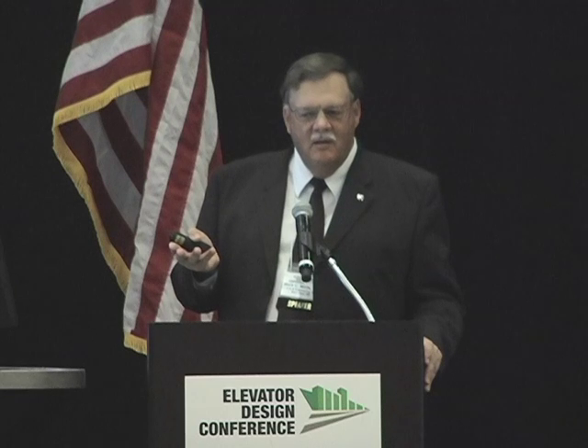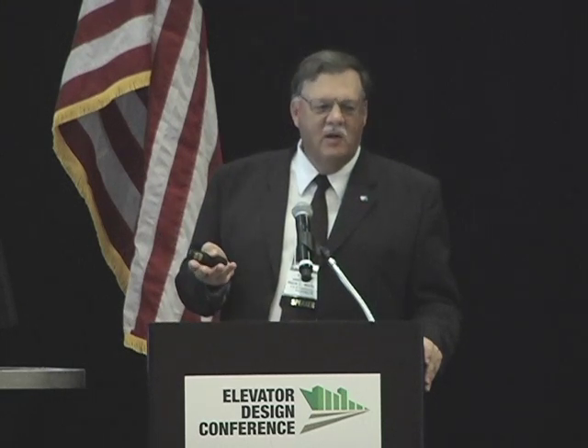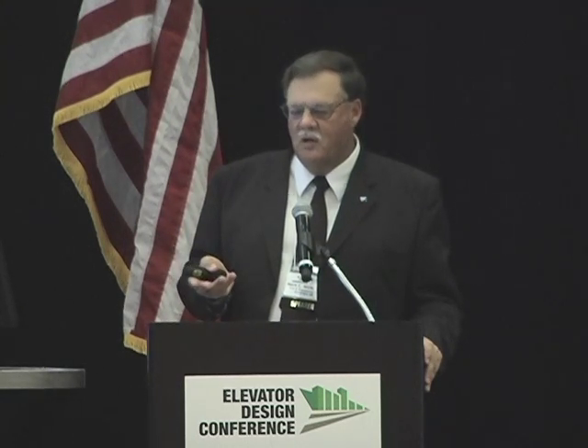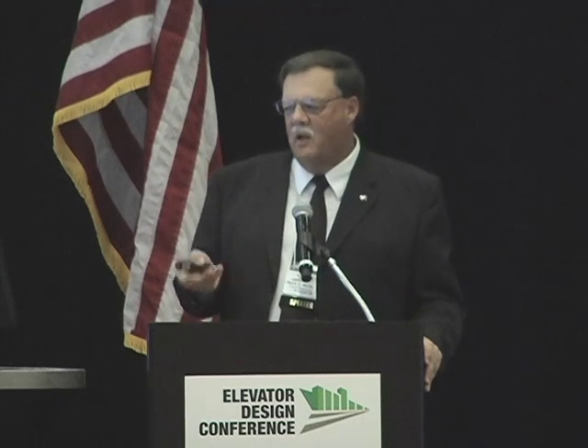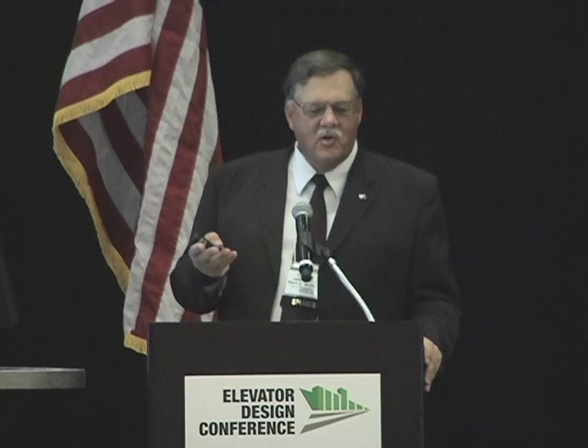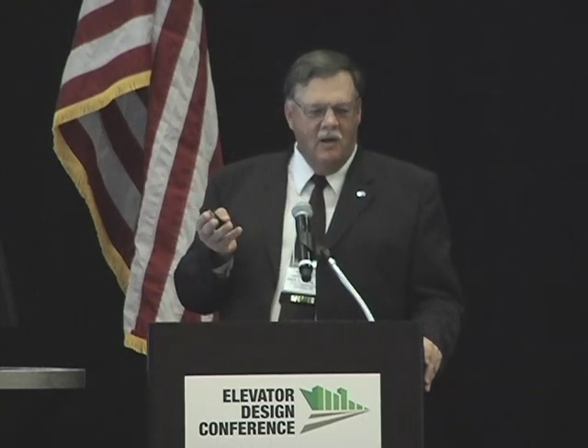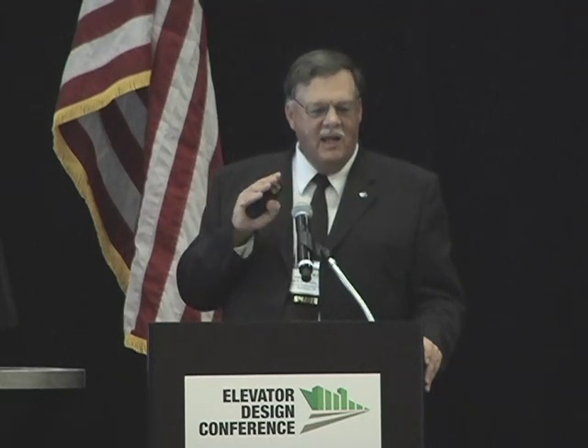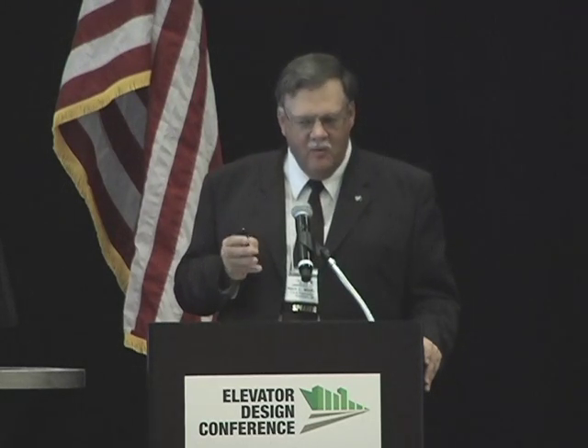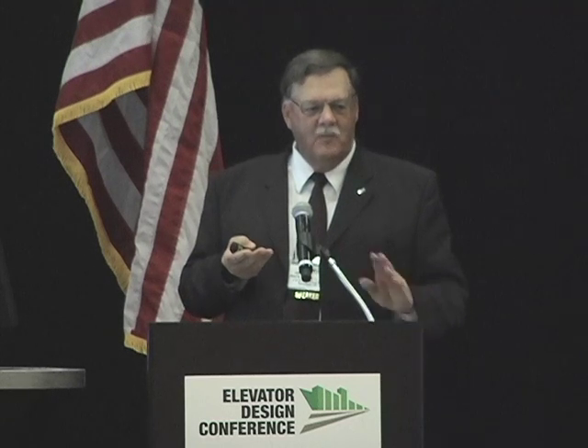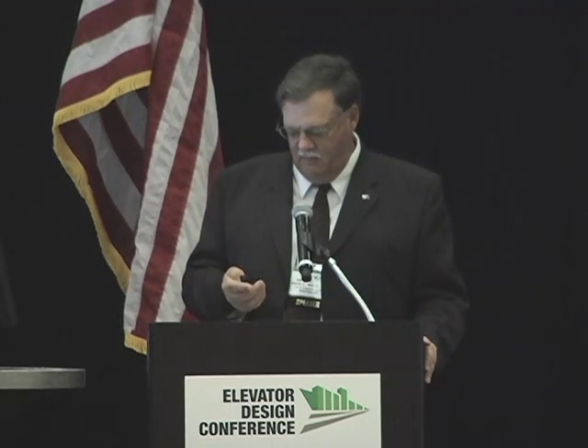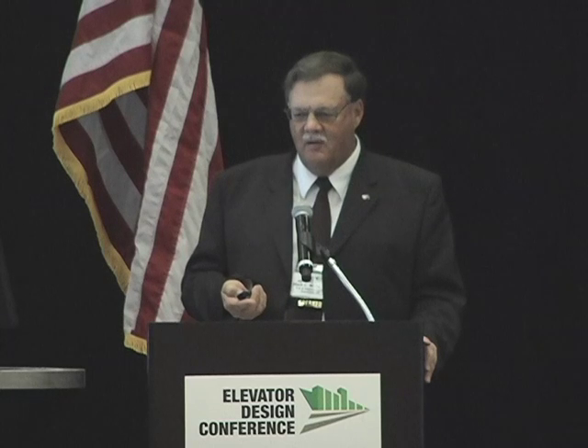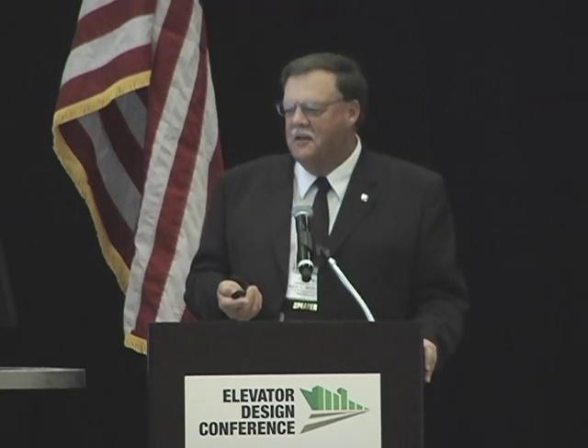Let alone the breaker itself is available with complete energy. You can get breakers now with built-in energy monitoring on that breaker, harmonics monitoring. You can even get remote communications, and you can actually tie in all your circuit breakers and not just have a meter on your main, but you could have energy monitoring and data on every one of your feeders if you want to. And I'm sure you'll love to sit around and just look at meter displays on your desktop, but those capabilities are here today.